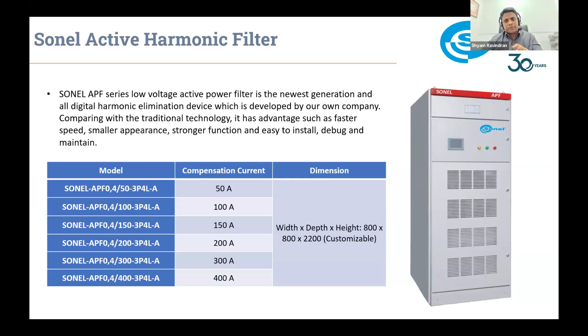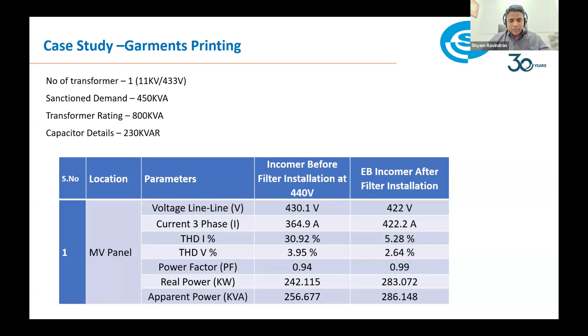Well, this is a textile company where we did a PQ audit. There was one transformer. The sanctioned demand was 450 kVA. The capacitors they had were 230 kVAR. They had a line incoming at 430 volts, the current was 364, and the THD percentage was about 30.92. So again, when you do an analysis within the customer premises, it's always THD. And the power factor at the customer premises was about 0.94.